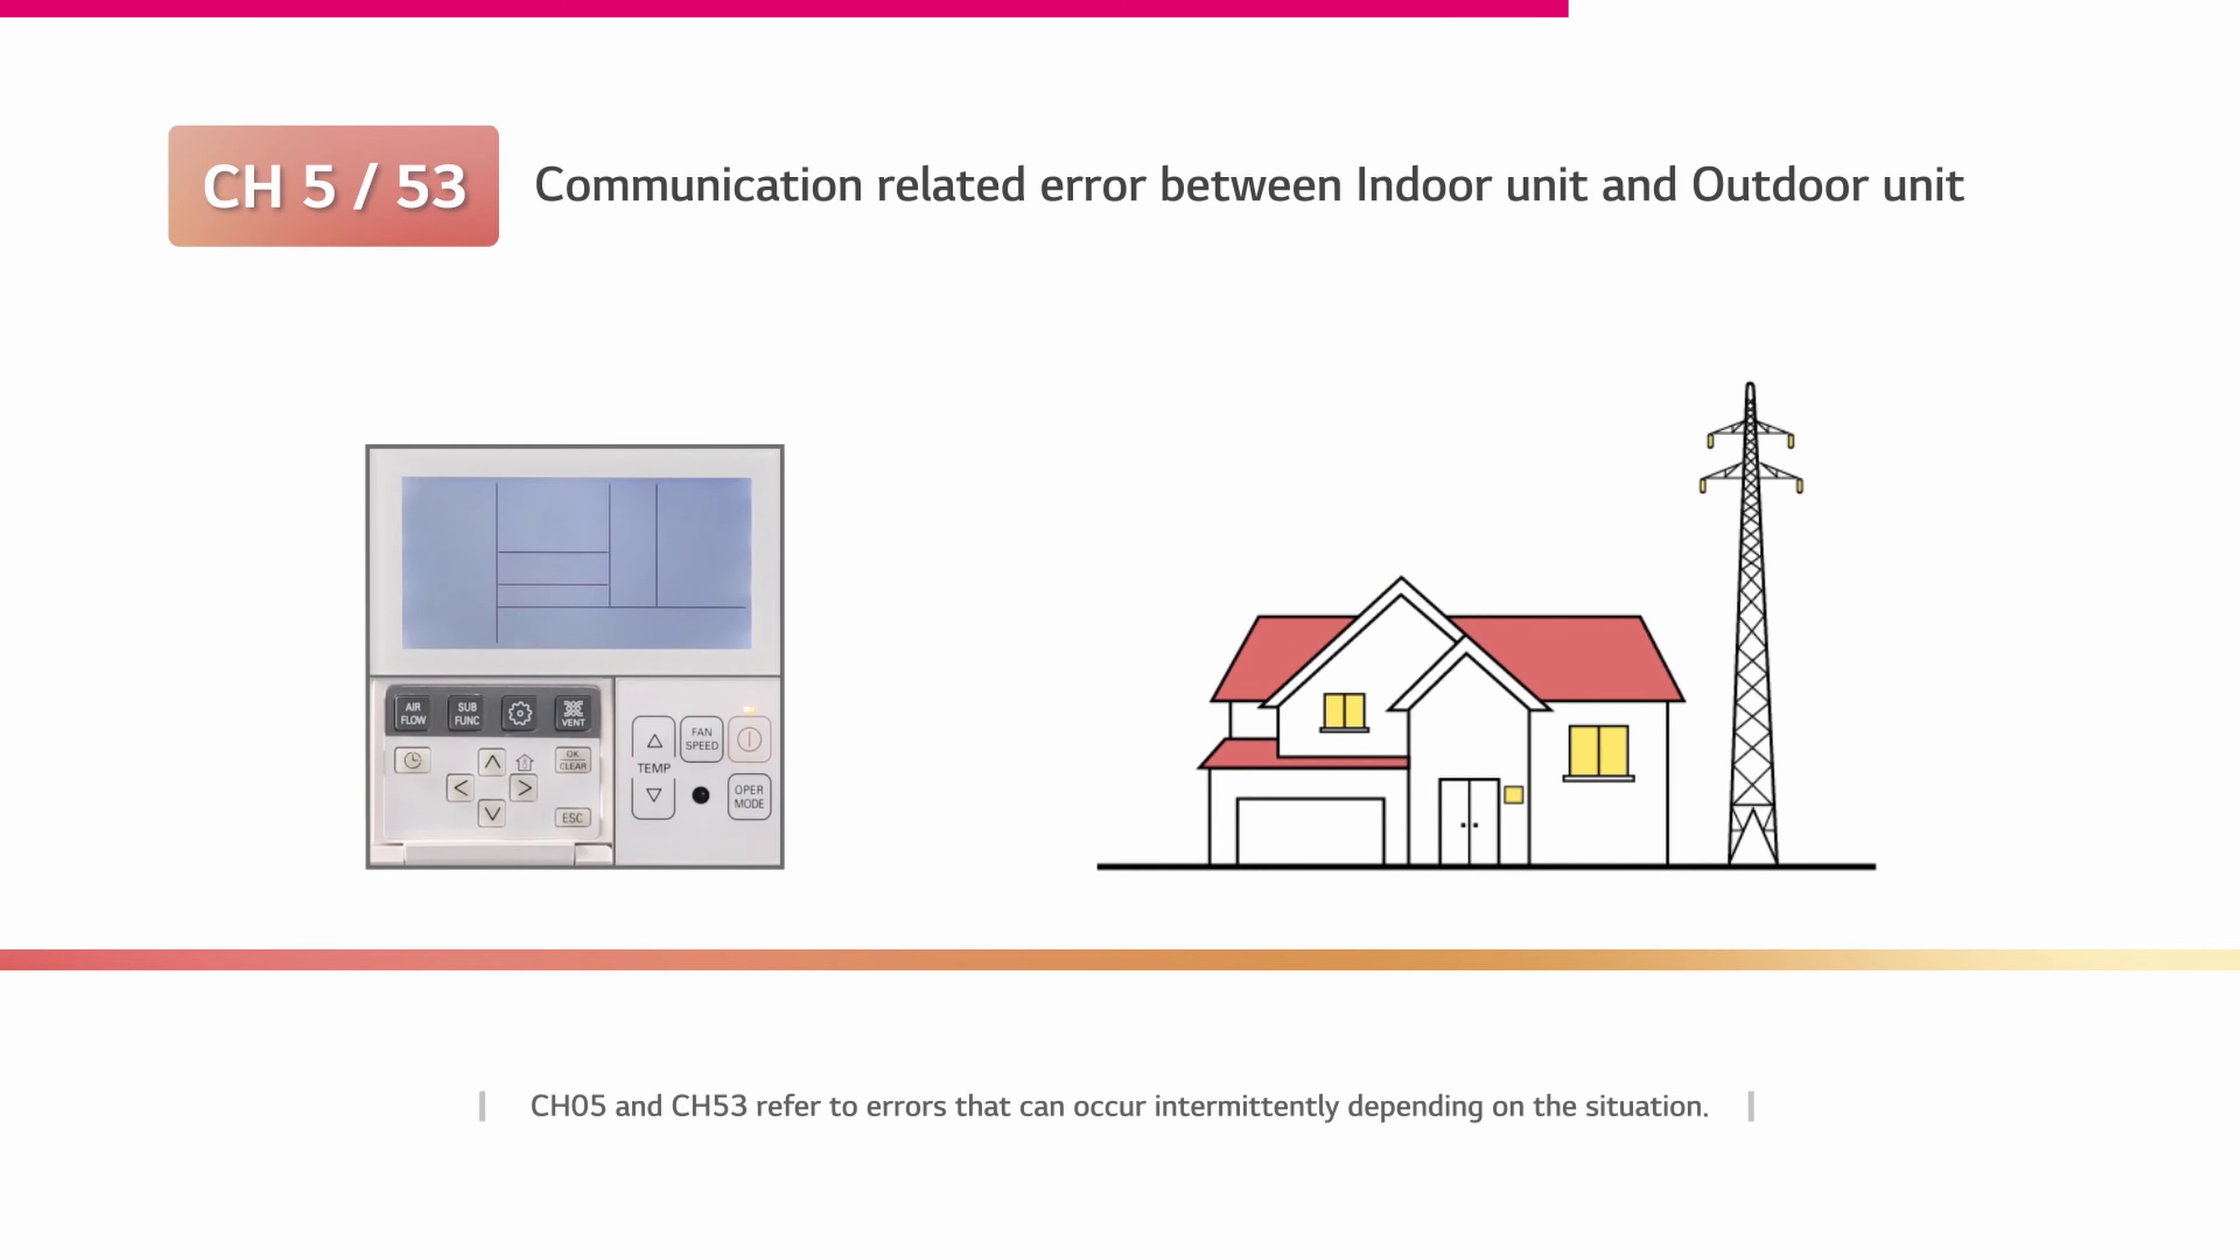Channel 5 and Channel 53 refer to errors that can occur intermittently depending on the situation. In this case, the error might stem from a surrounding load. Check if the error was caused by interference from other electrical installations. Also see if the same communication error occurs when only the product is operated after turning off other electrical, communication and security devices and lighting.